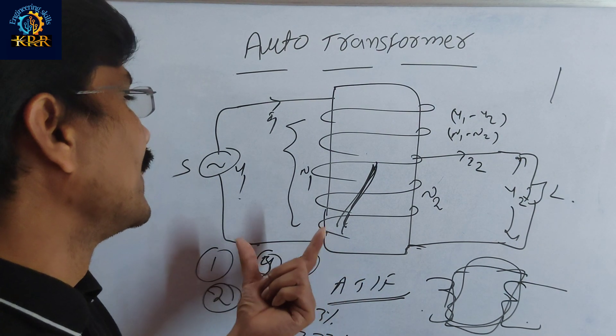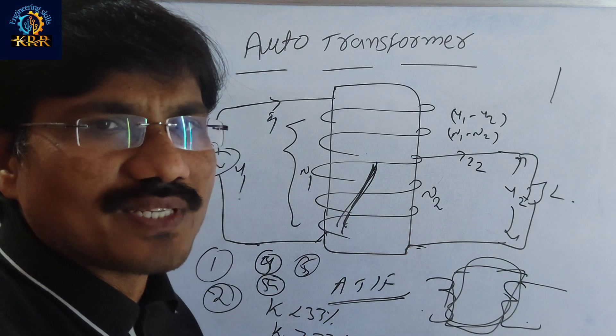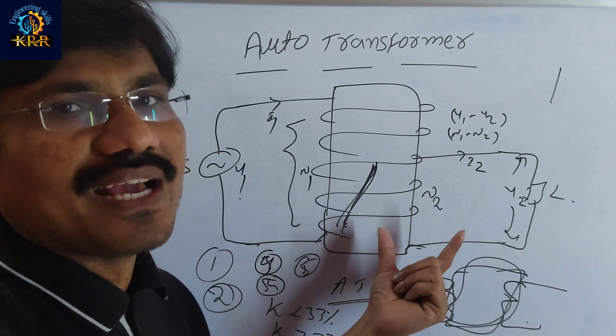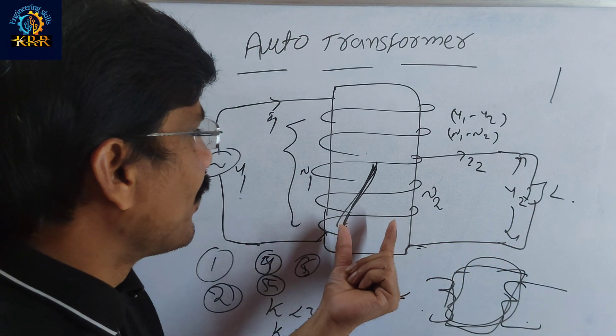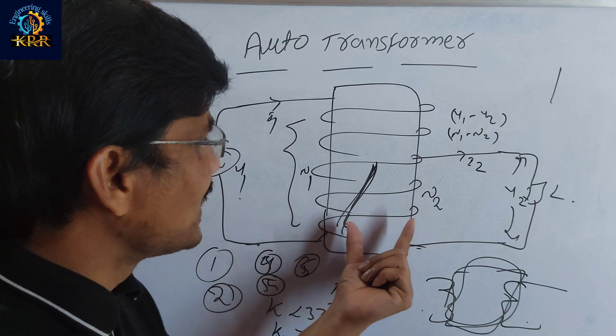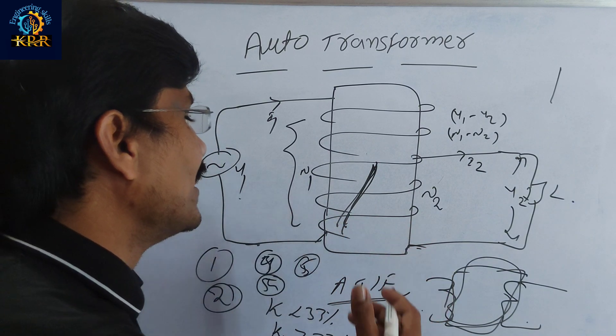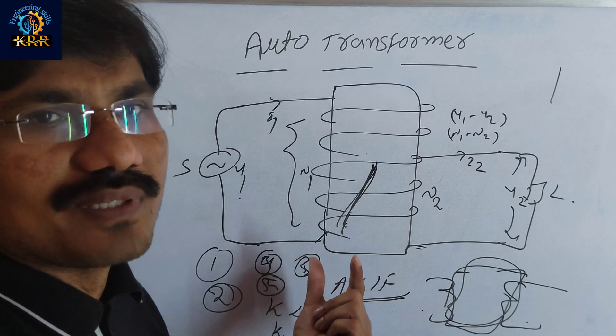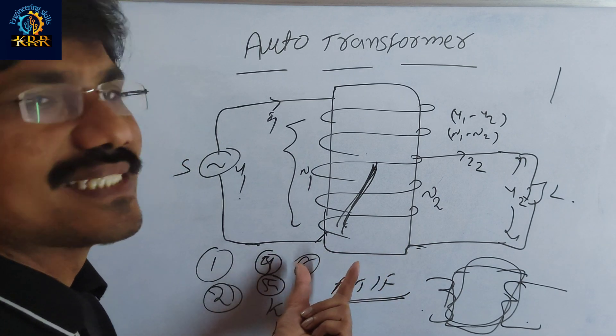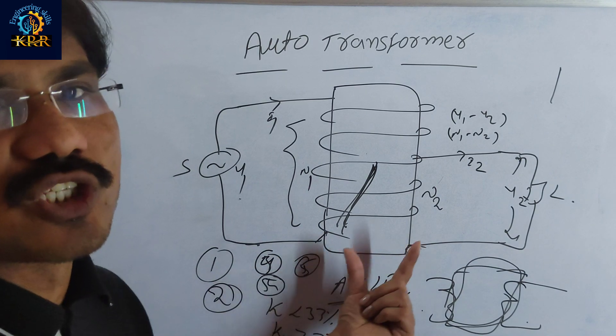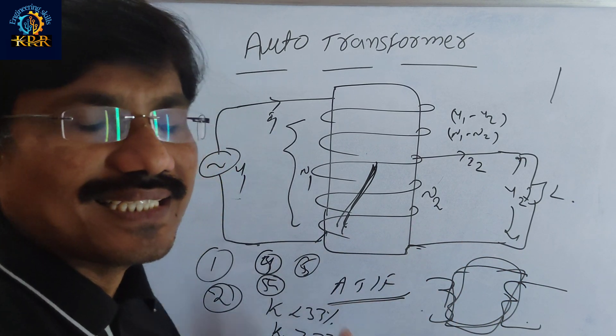Another drawback is that the percentage of impedance is low in an auto transformer, so the short circuit current will be high. In an auto transformer, the leakage flux is less, which means the impedance is less. Less impedance means a lower percentage of impedance, and therefore the short circuit current will be high.